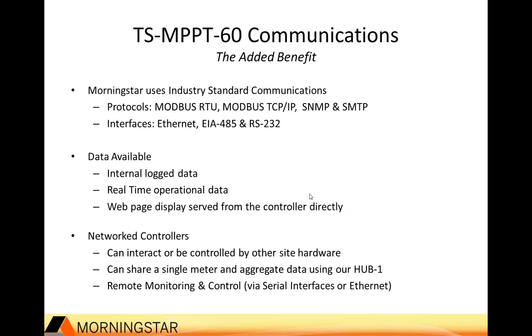To talk a little bit about the communications, this product uses the standard communications suite that we've offered on the other TriStars, and that would be Modbus communication protocol, both Modbus RTU as well as Modbus TCP/IP. That's broadcast over Ethernet. We also utilize SNMP for telecom folks out there, as well as SMTP for email notification. The interfaces are an Ethernet port and also RS-232 and 485.